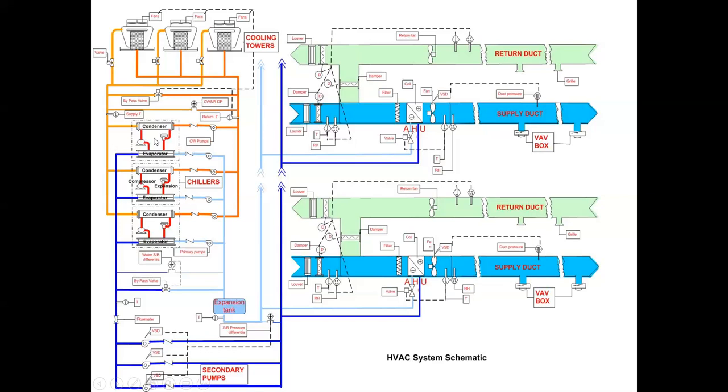It might be 38. It can't be below 32 or we're going to start freezing water, unless we've got glycol in it. So if they're just handling water, then it's got to be 37, 38, something like that. Then the refrigerant goes into the evaporator. That's where the cooling effect occurs. We boil that refrigerant back into the superheated vapor state at low pressure, and it goes back into the compressor. Round and around she goes.